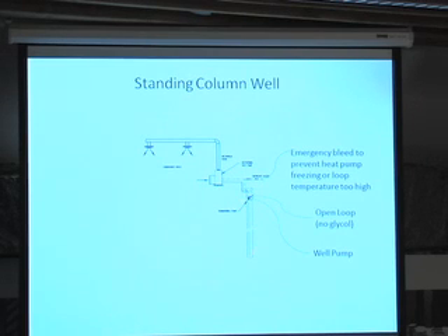The pump pumps water from the bottom of the well, pumps the water through the heat pump here, and the water dumps back at the top of the well. So basically you're utilizing the whole depth of the well as a heat exchanger. It's open. You're using the well water directly in the system.